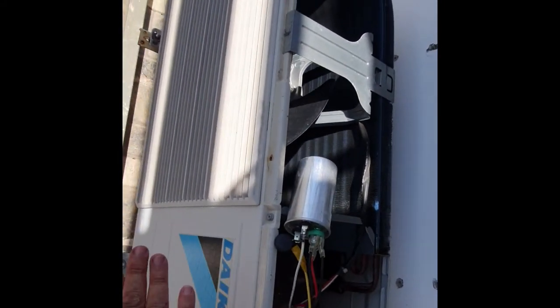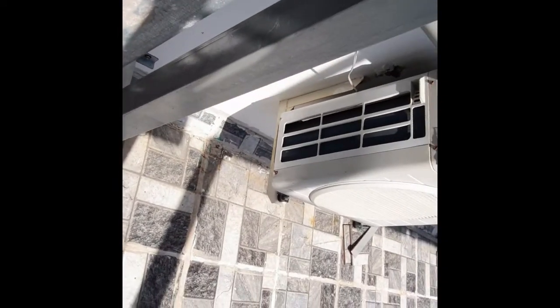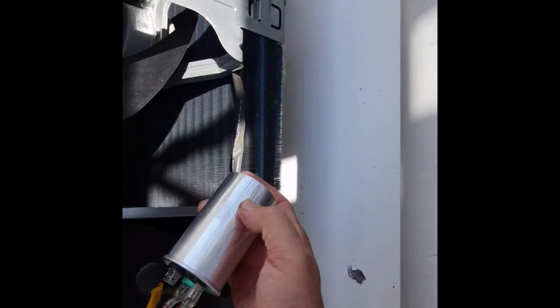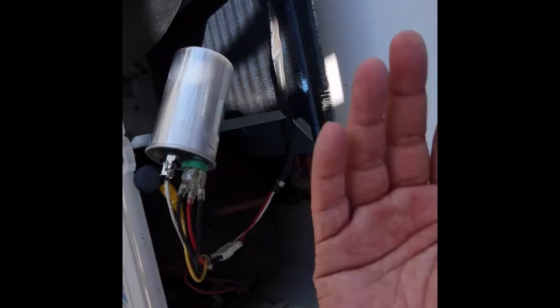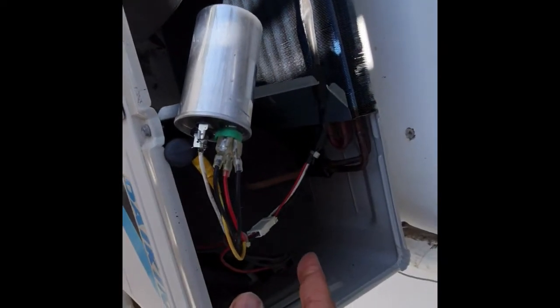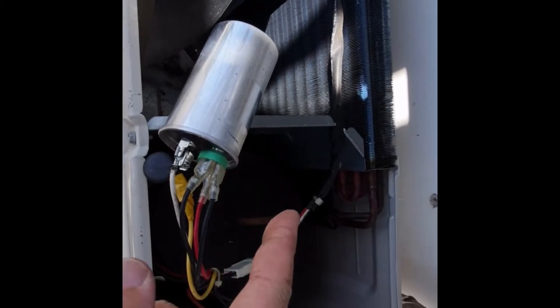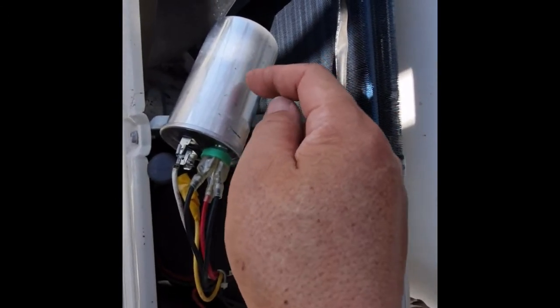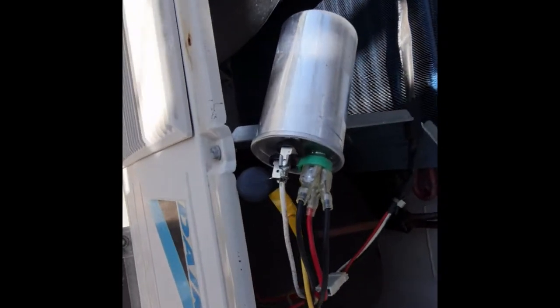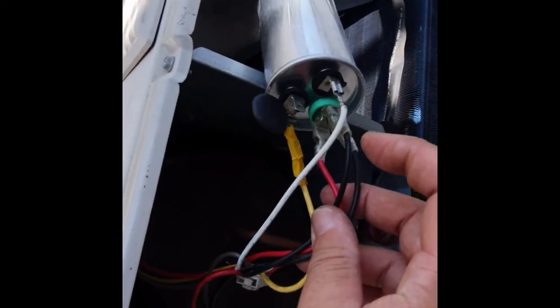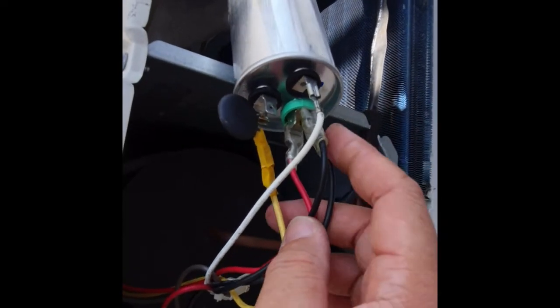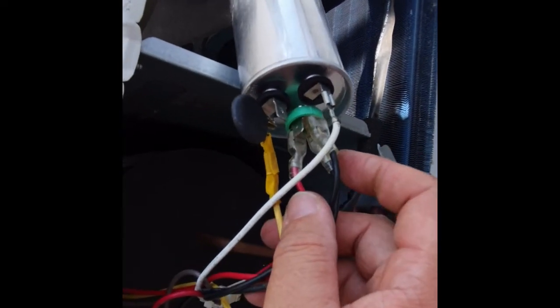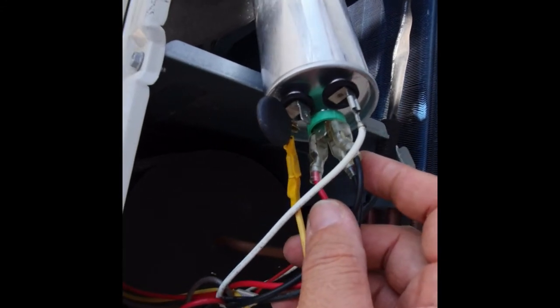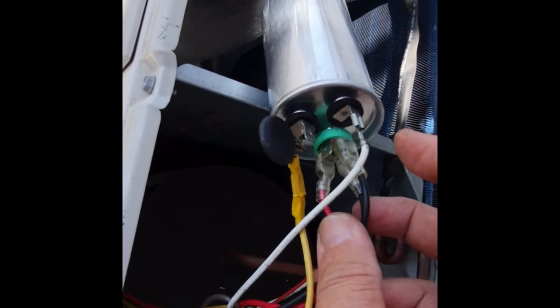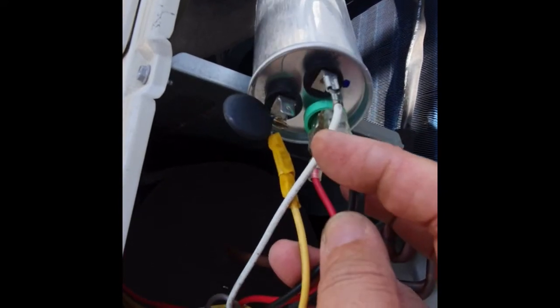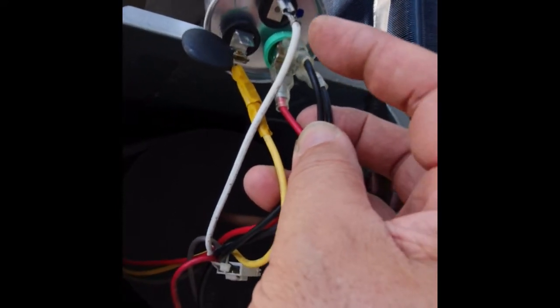Hi guys, this is an AC unit. All my AC units are installed with this so-called NTC. When you open up, you can see this is the old type. Only the old type can use this, not the inverter type. You can see this capacitor. This is a start and run capacitor. There are three legs. This is the common, of course. The fan and the compressor are all connected to this, so this should be common. One of them is run, and one of them is the start current.